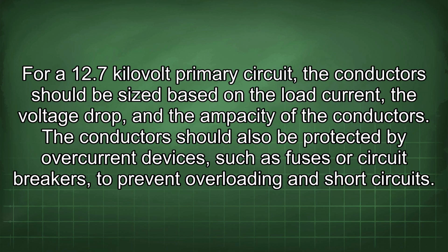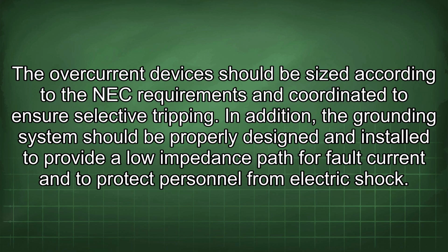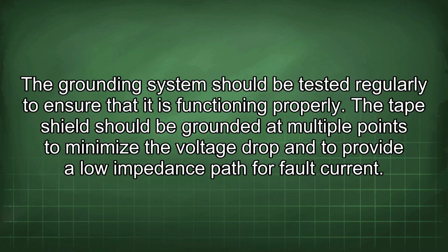For a 12.7 kilovolt primary circuit, the conductors should be sized based on the load current, the voltage drop, and the ampacity of the conductors. The conductors should also be protected by overcurrent devices such as fuses or circuit breakers to prevent overloading and short circuits. The overcurrent devices should be sized according to the NEC requirements and coordinated to ensure selective tripping. In addition, the grounding system should be properly designed and installed to provide a low impedance path for fault current and to protect personnel from electric shock. The grounding system should be tested regularly to ensure that it is functioning properly.